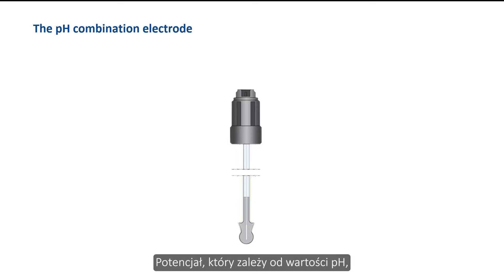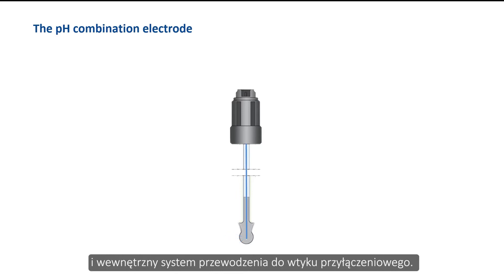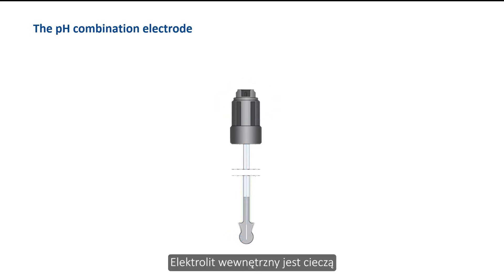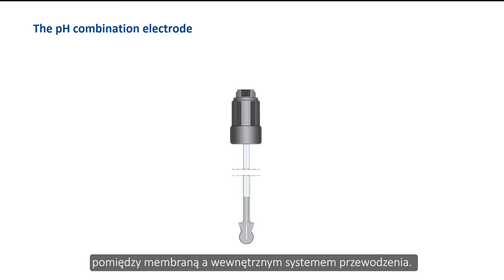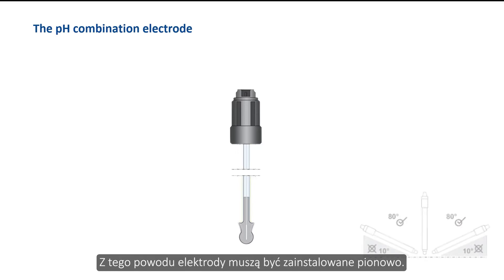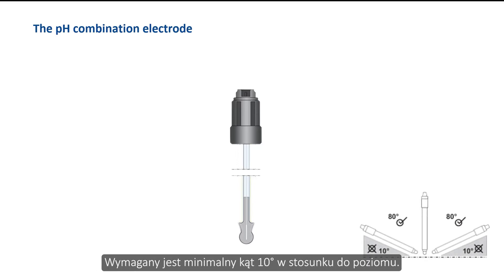The potential which depends on the pH value is led via the inner electrolyte and the inner conduction system to the connection plug. The internal electrolyte is liquid and is responsible for the connection between the membrane and the inner conduction system. For this reason, upside-down measurements are not possible with combination electrodes — a minimum angle of 10 degrees to the horizontal is required.